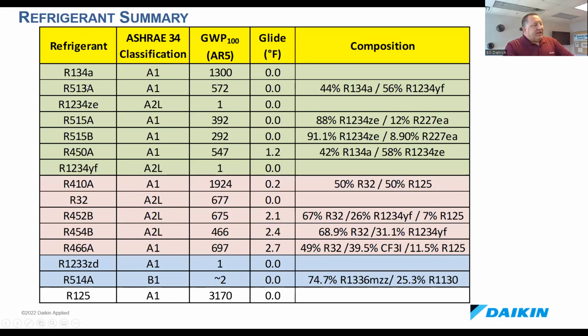And in the ASHRAE designation, if a refrigerant has a 400 or a 500 series number, it's a blend. And then generally at the end of those blends, they have capital letters to designate if it's a slightly different blend, right? And in the ASHRAE designation, if it's a 500 series, it's been determined to be what's called an azeotrope, which just means in that specific blend, it behaves as a single working fluid over a pretty wide range of temperatures and pressures. So even though, for example, R513A is a blend, you can pretty much treat it as a single working fluid because it doesn't have any what's called temperature glide.